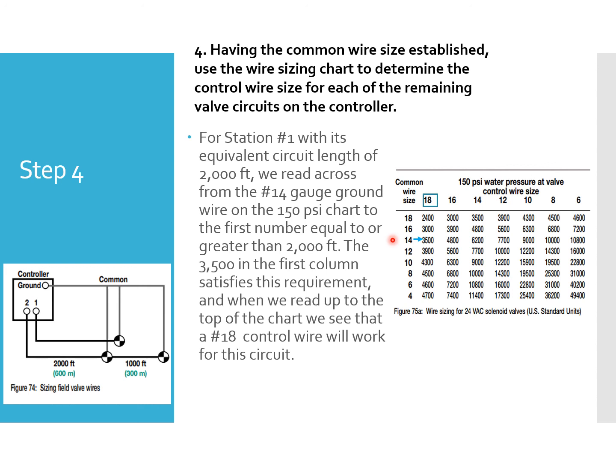So since we already have a 14 gauge common wire, we're going to scoot over and see what is the first size wire from left to right that meets the requirement of at least 2,000 feet. So the very first one is the smallest wire on here, which is 18 gauge. We come over and we cross it with the common wire and see if it meets that requirement. And it does. It has a maximum run of 3,500 feet. So there's no need to look any further.